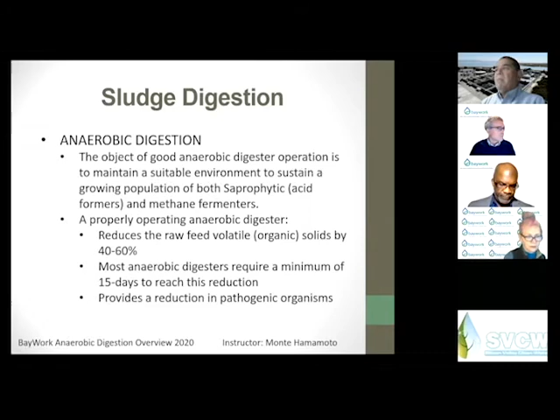One of the regulations we follow that regulates the formation and disposal of biosolids is 40 Code of Federal Regulations, Part 503, which has a process to significantly reduce pathogens called PSRP. It states that biosolids are treated in the absence of air, which is anaerobic, for a specific mean cell residence time, meaning how much time it spends in that environment at a specific temperature. They want 15 days residence time at a temperature between 35°C and 55°C, or 60 days at 20°C.